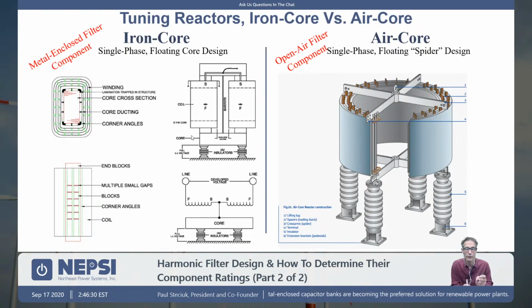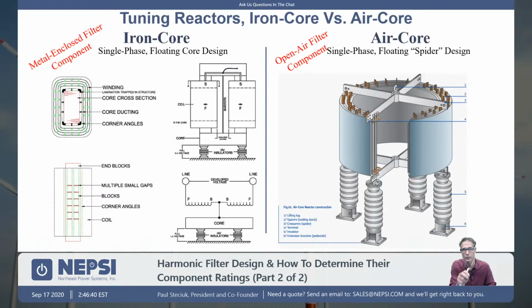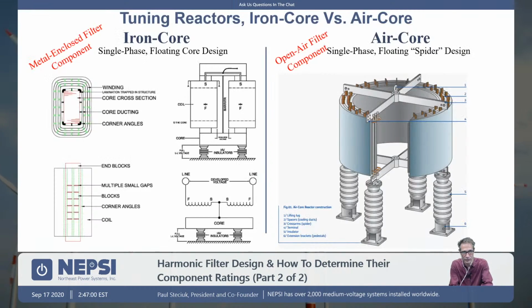And if you were to go through the calculations, what you would determine is that the voltage drop across a harmonic filter reactor is about 1 over n squared, 1 over the tuning point squared, times the line-to-neutral voltage. So a fifth tuned filter is just a roughly maybe 5% voltage drop across the reactor. Therefore, there is an advantage to putting reactors, single-phase reactors, up on insulators. It means that the majority of the voltage drop is dropped across the insulators rather than across the windings.